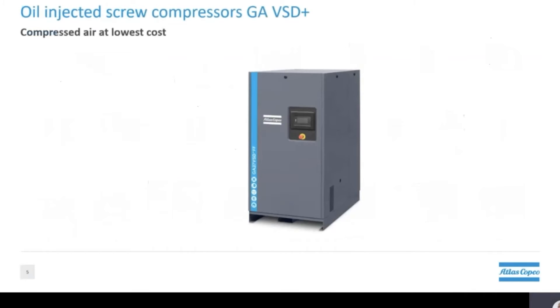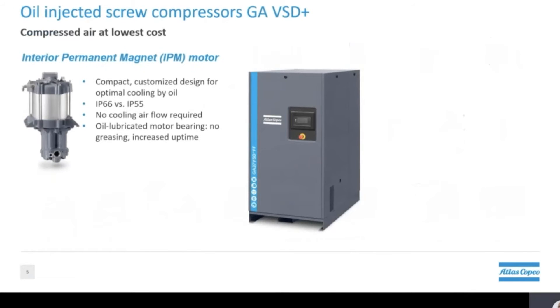First up we have our variable speed oil injected screw compressor — as this is a mouthful, we simply call it our GA VSD+. Our first innovation is the introduction of Atlas Copco's patented design of the interior permanent magnet motor, or IPM motor for short. This design is compact and uniquely tailored for optimal cooling using oil and not air. Oil lubricated bearings mean that no re-greasing is required, which in turn increases uptime of the compressor — perfect for minimizing production time loss.